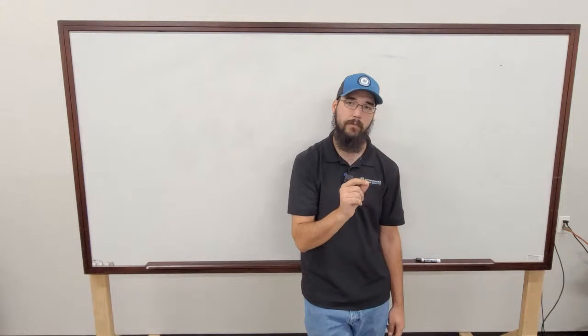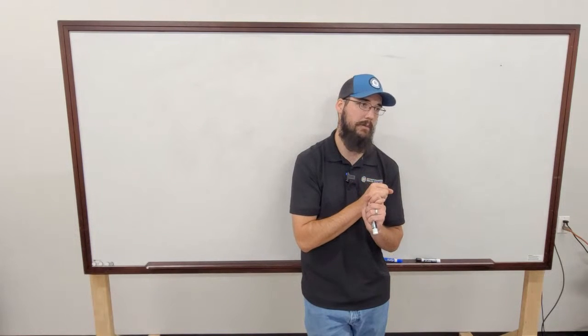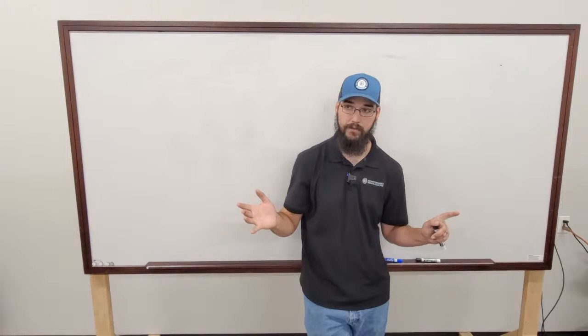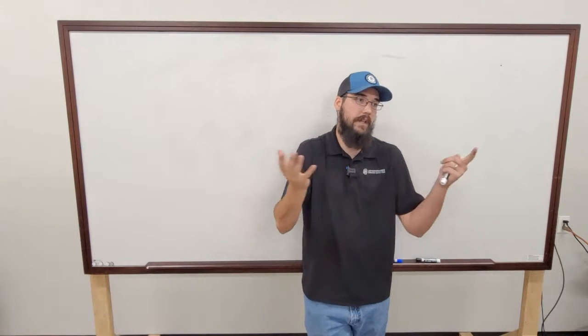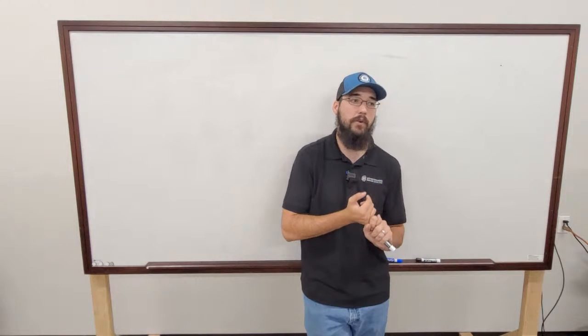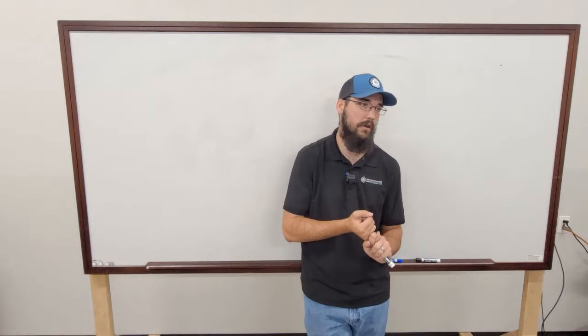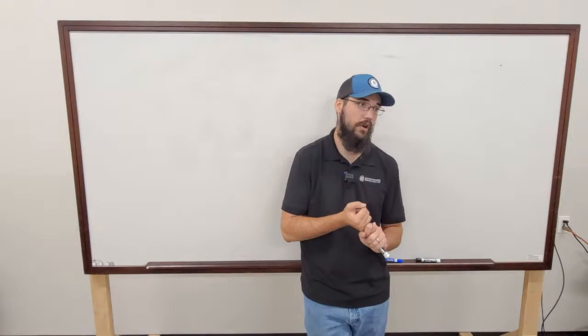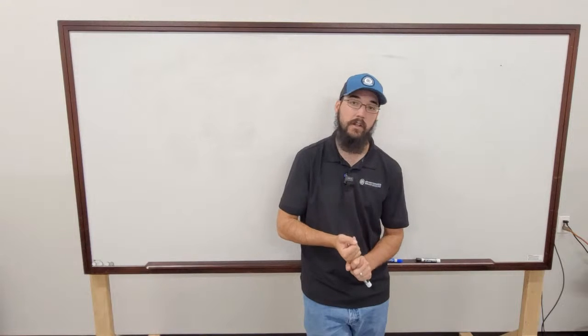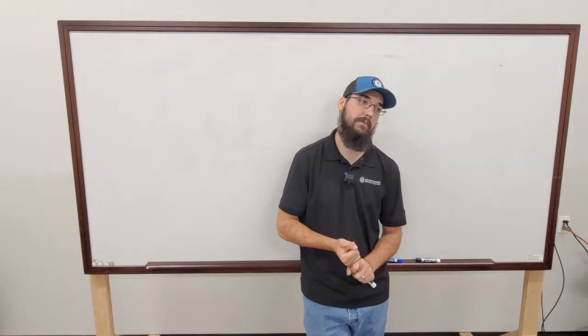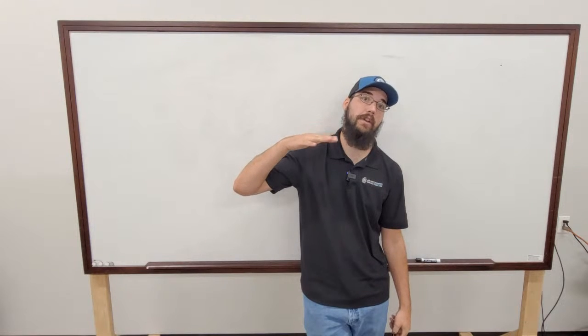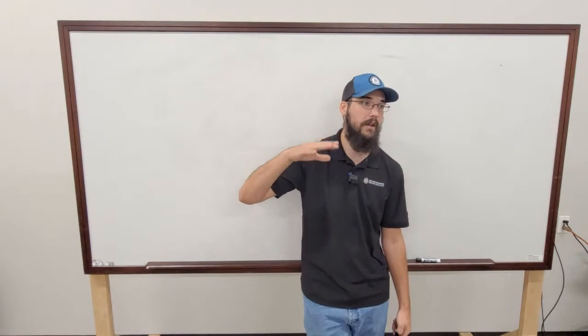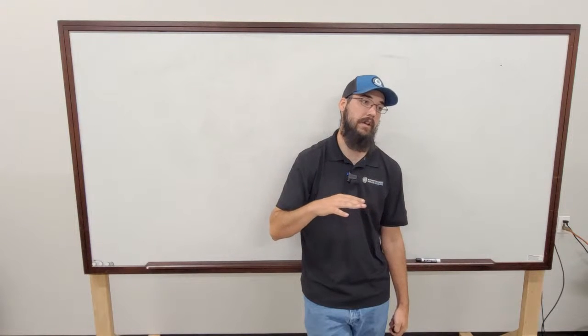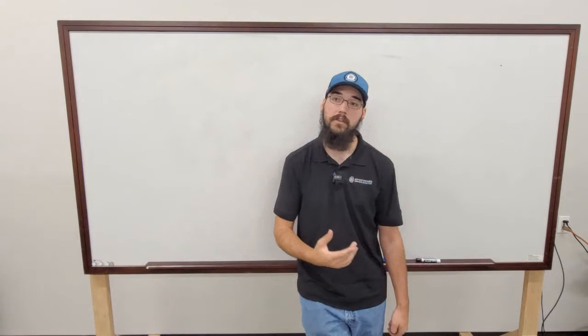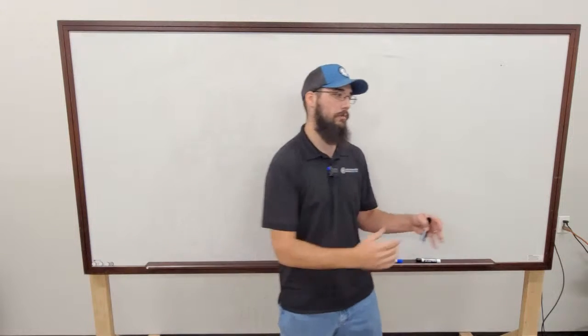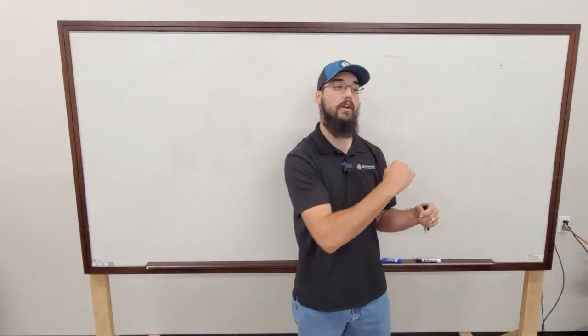And what that will lead to is you can have a suction limit pop up, even during pull downs. So if you're in a startup state and going into a pull down, and even before you get to your pull down RLA limit, or current limit, you might see a suction limit pop up on your display. And that's because usually that's around 30 to 32 degrees of saturation, somewhere in there. It'll go into a suction limit, and that's because your EXV has to be able to catch up. So one of the things that can happen is, the machine turns on, is starting to ramp up, you see it goes into a pull down.